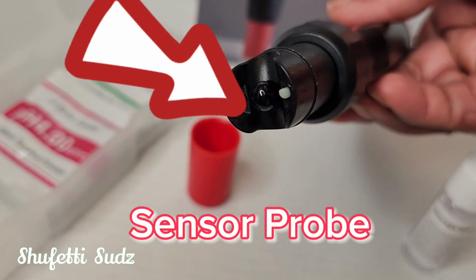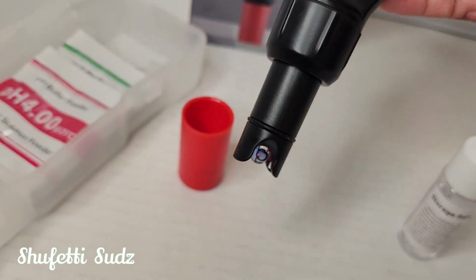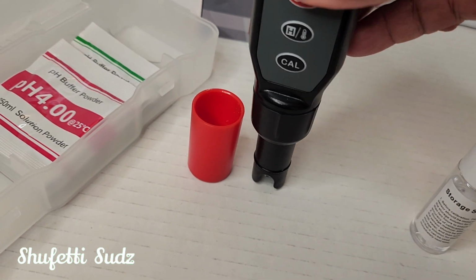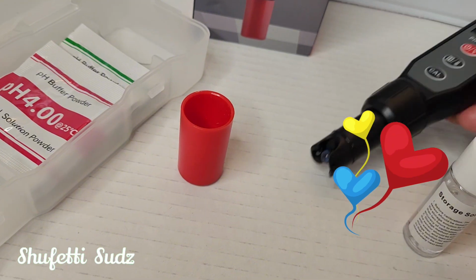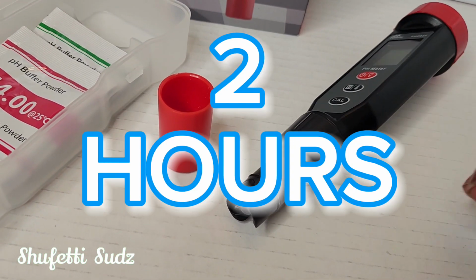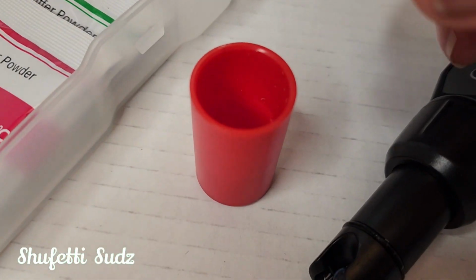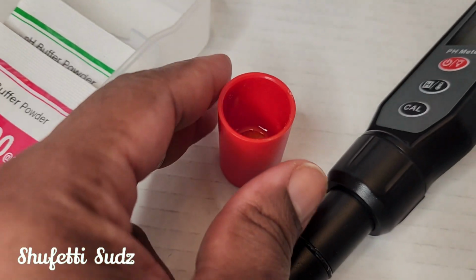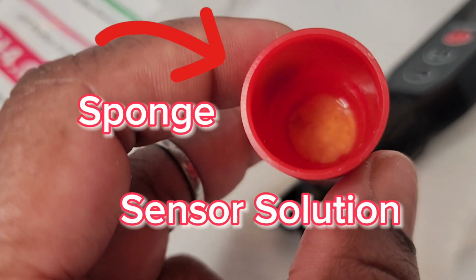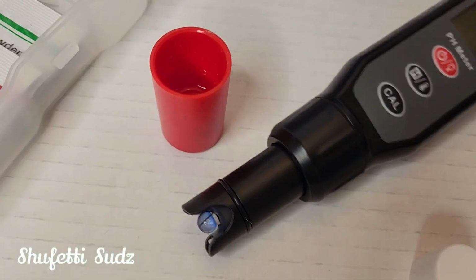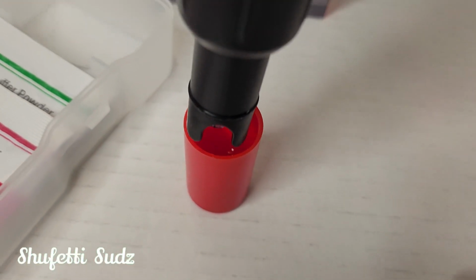Before the first use, put enough storage solution into the cap to cover the sensor and let it soak for 2 hours. Do not store the probe dry or in water. It must be stored in an upright position using the storage solution.